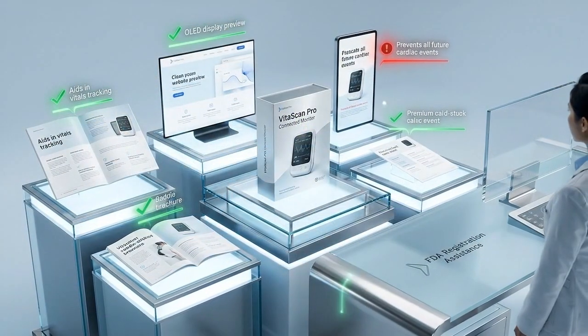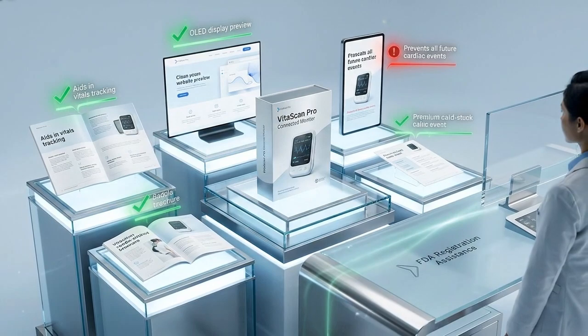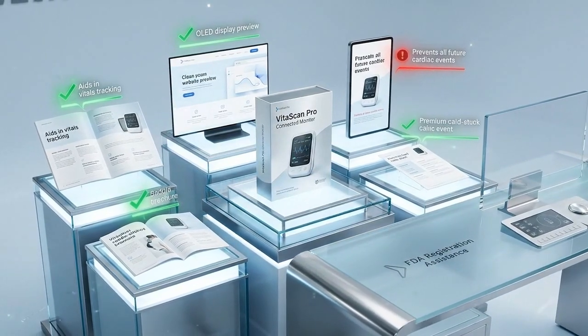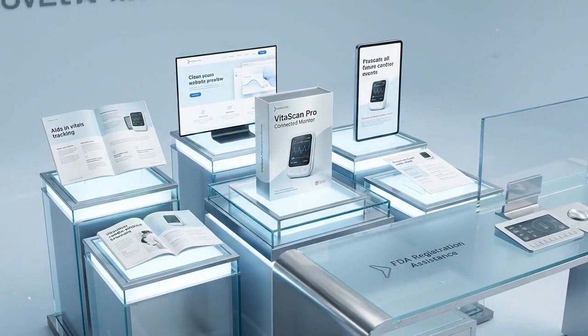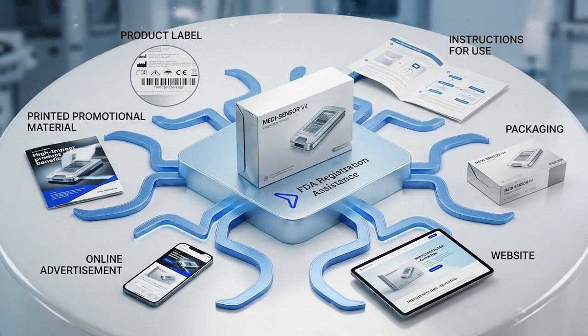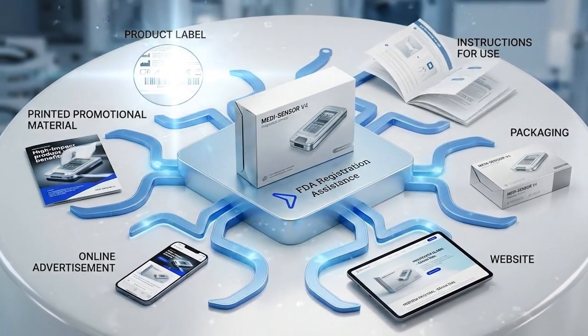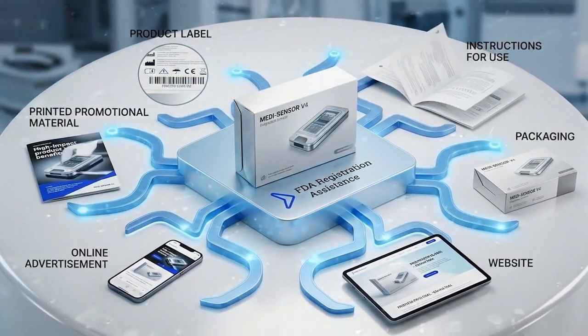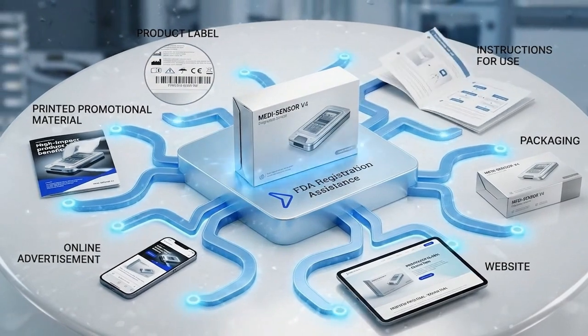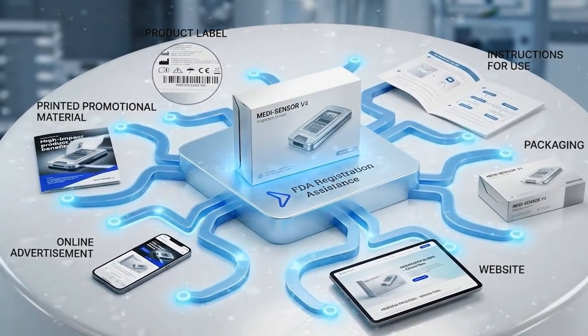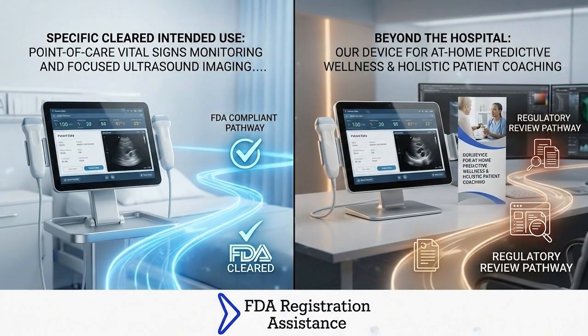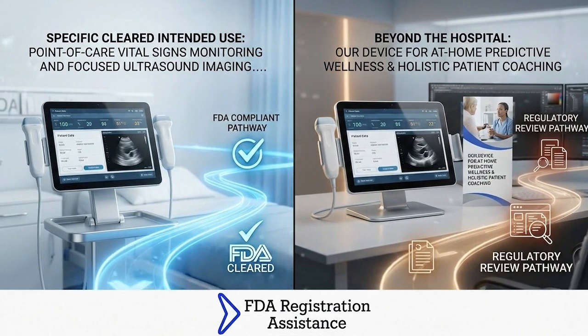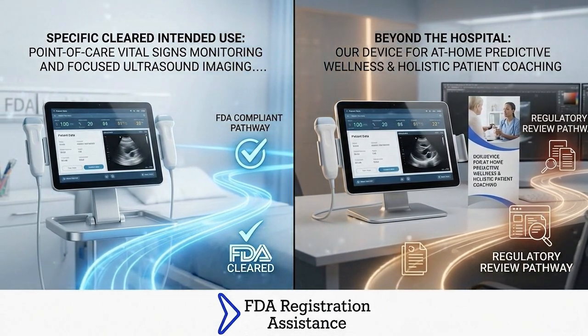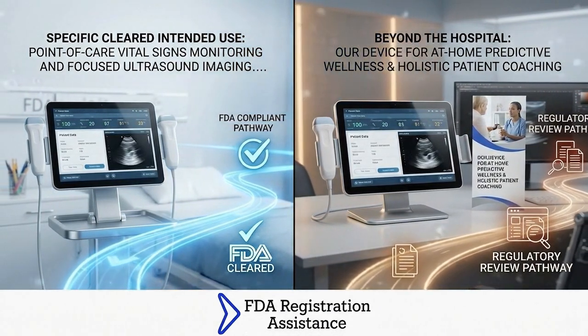One of the most common labeling mistakes involves product claims. FDA evaluates medical devices based heavily on their intended use. That means statements appearing on labels, instructions for use, packaging, websites, advertisements, and promotional materials can all influence how FDA views the device. Claims that extend beyond the device's authorized intended use may create regulatory concerns and potentially change the device's classification or regulatory pathway.